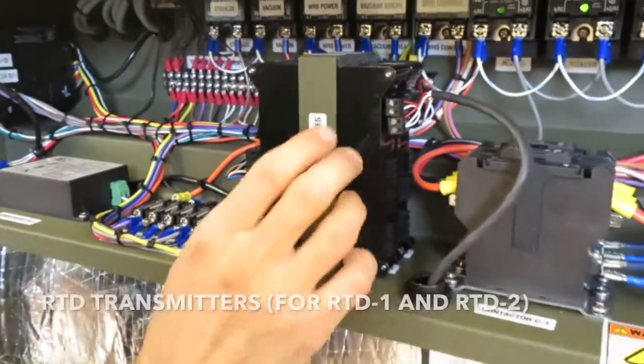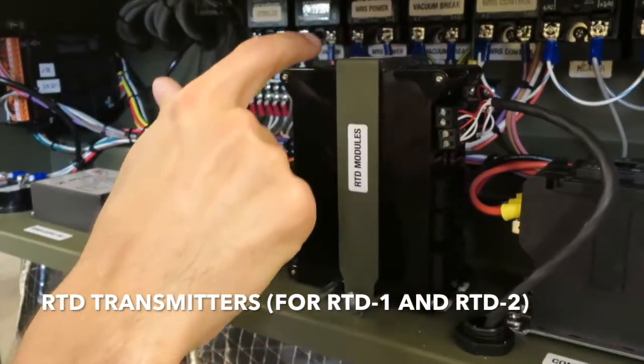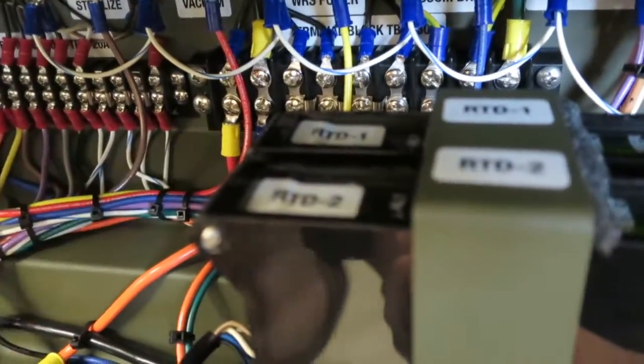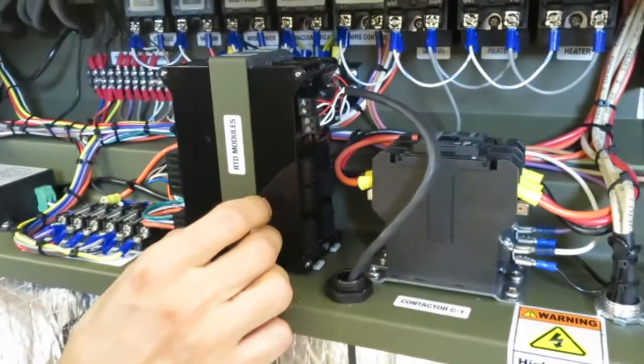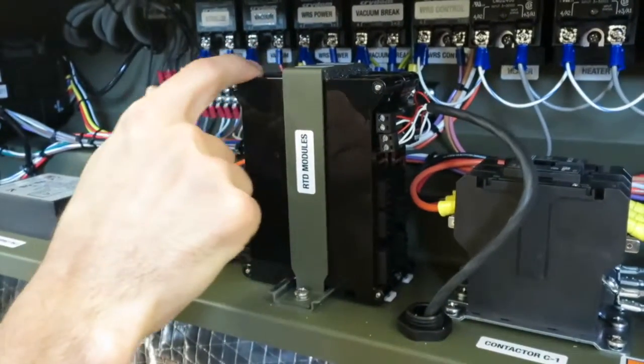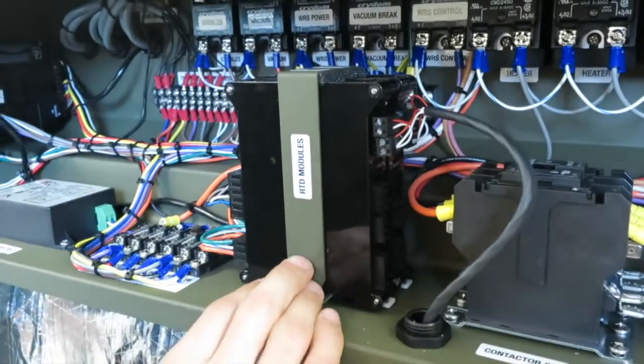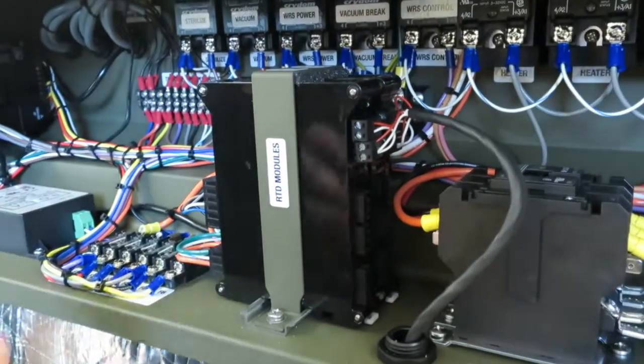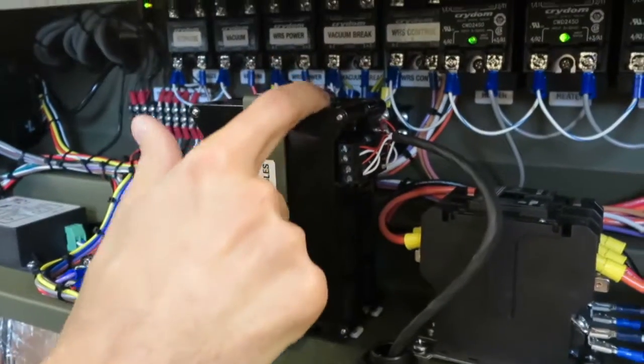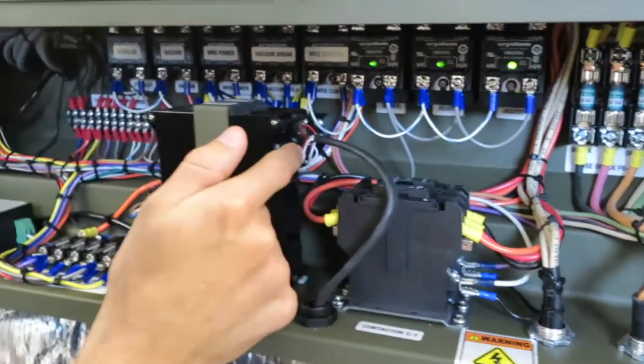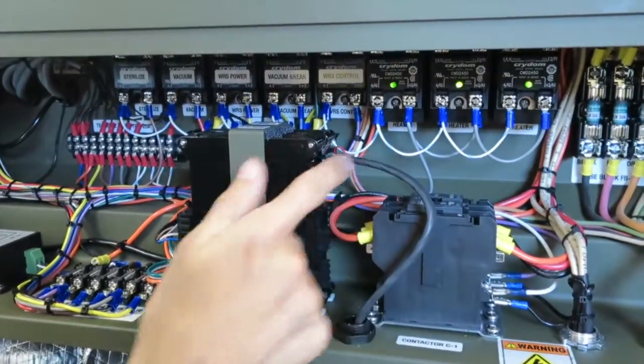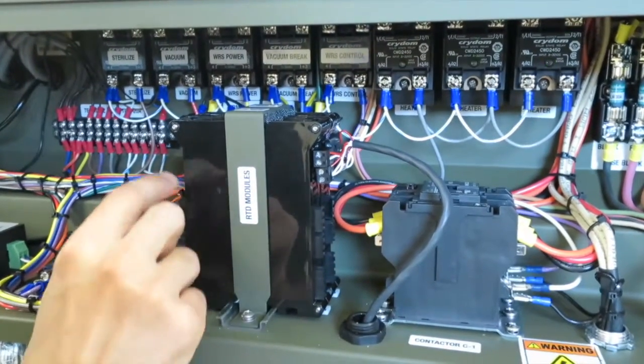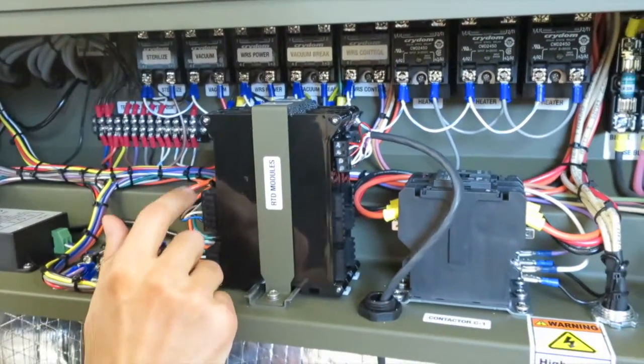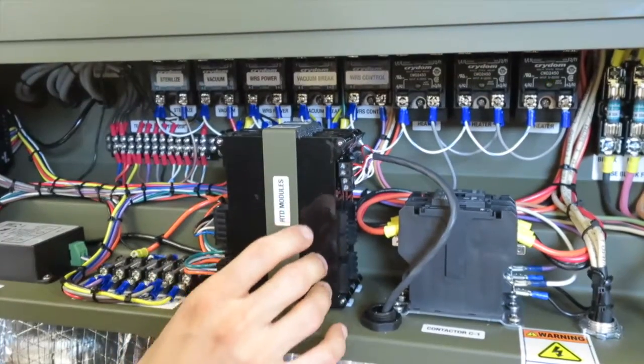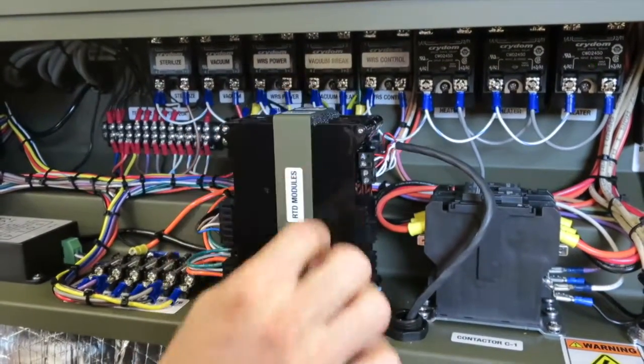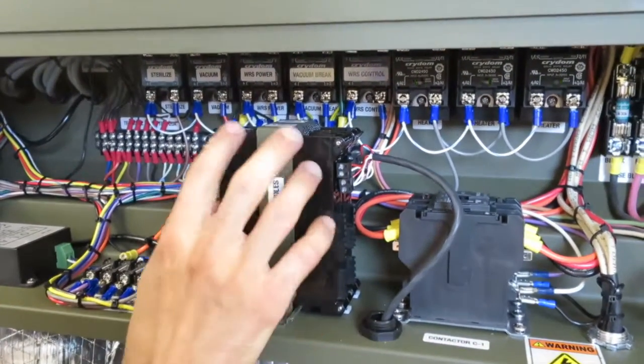Right here we have the RTD modules or RTD transmitters. There's a number 1 and number 2. Again, the number 1 is correlated to the number 1 element in the RTD probe. That's what the sterilizer is controlling off of. Number 2 is constantly checking it. So during a cycle, during exposure, number 2 is checking up on 1 and making sure it's reading the correct temperature. These transmitters right here are very important. Here on the input side, we have an analog input coming from the RTD probes. On the output side, it's a digital Modbus output that is sent to the PLC. So these are very important for reading temperature and very easy to change out, just removing a couple screws. Very important for your temperature readings.